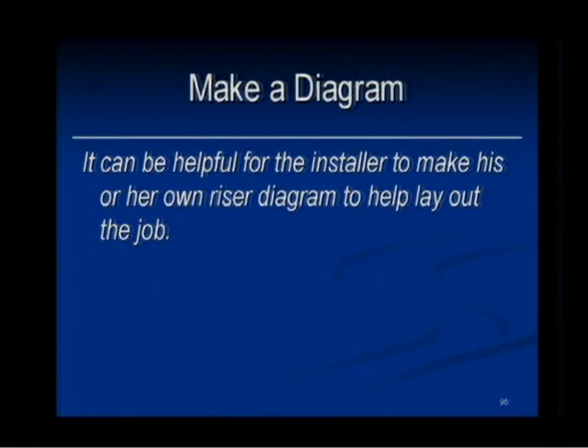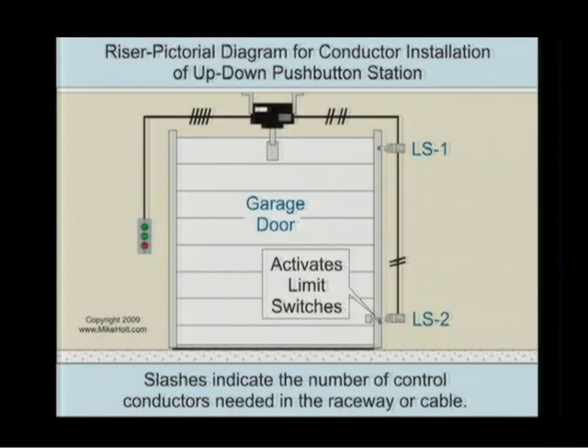It can be helpful for the installer to make his or her own riser diagram to help lay out the job. Here's an example: if you were going to be using the limit switch down, the limit switch up, and a start push button, you hand draw this out and get your wiring and say, okay, now I know what I'm running and when I'm running. That's what I did when I pulled wire. I just knew what I was doing in advance, and you just pull it in there, and then you make your terminations, and then you take one stage at a time.